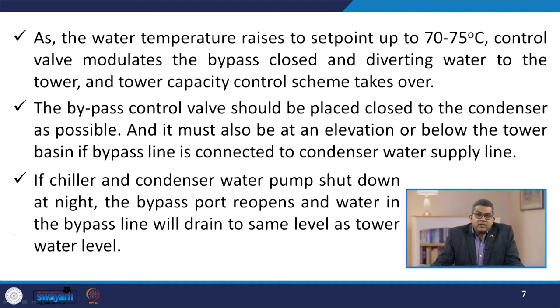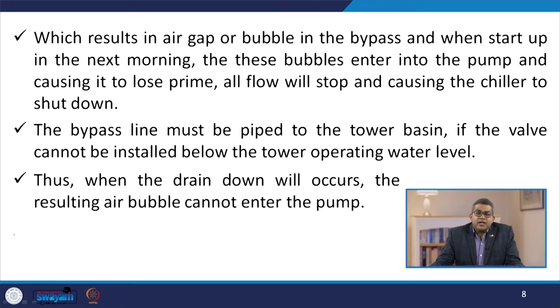Sometimes, if the chiller and condenser water pump shut down at night, the bypass port reopens and water in the bypass line will drain to the same level as the tower water level. This can result in an air gap or bubble in the bypass. When starting up the next morning, these bubbles may enter into the pump, causing it to lose prime. All flow will stop, causing the chiller to shut down. Therefore, sometimes priming may be required.